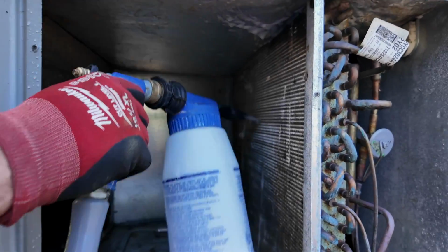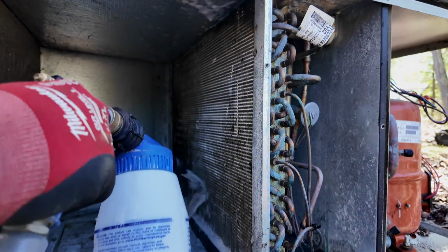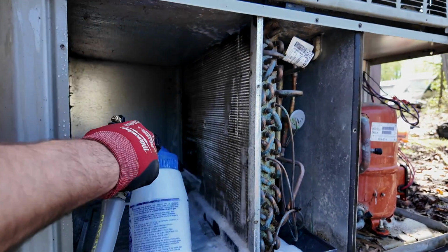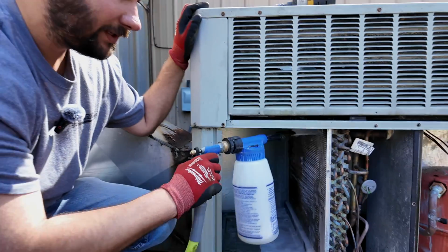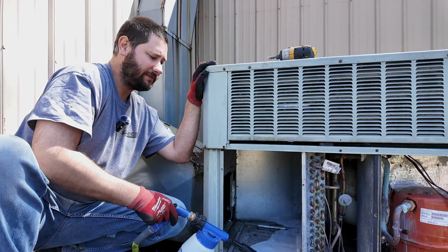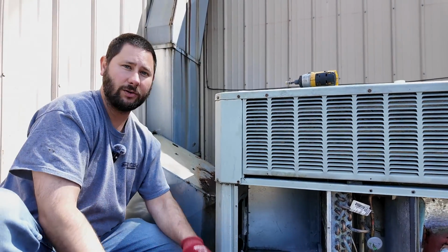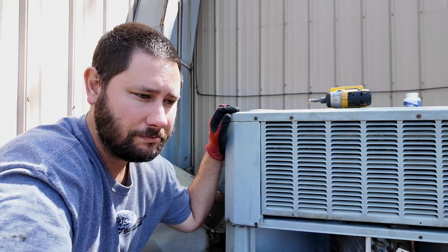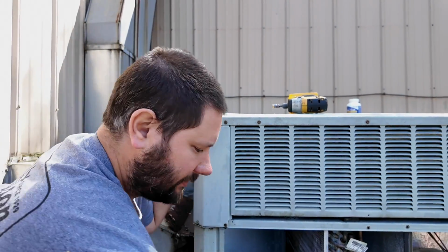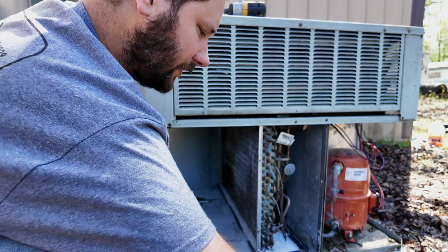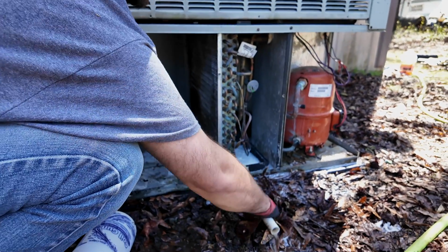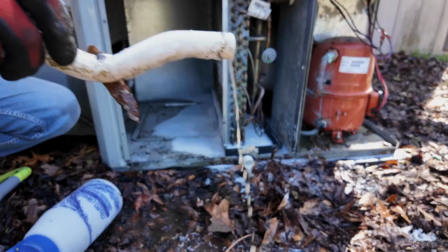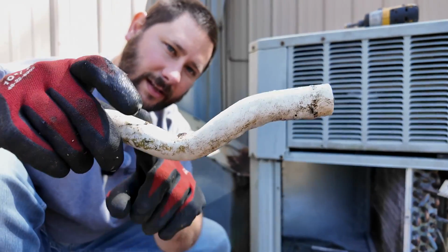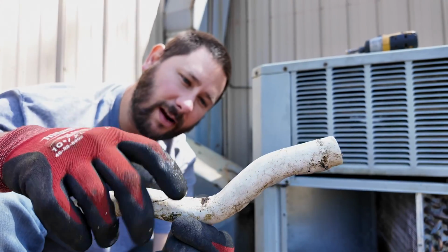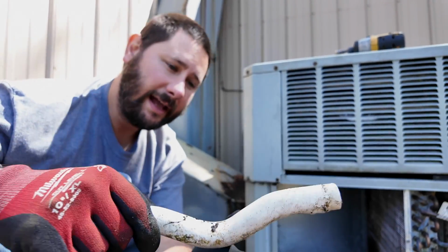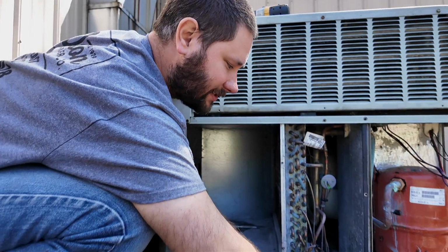And this is a copper with aluminum fin. Be careful, this is sharp. Don't go putting your hands on the aluminum. Also, something that's very, very important when it comes to indoor coils, especially when you have a split unit, maybe it's in your attic, in your basement, it's a gas furnace or an air handler, you want to make sure you clean out your trap. This right here is a trap. And where you have the little drop here, this is where sediment can accumulate. And if this gets backed up, then your water is going to stay inside your pan.